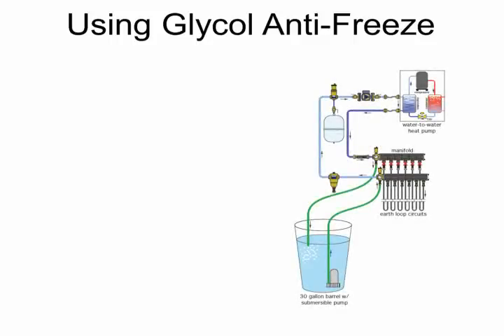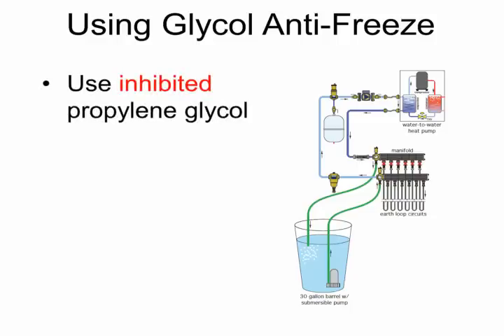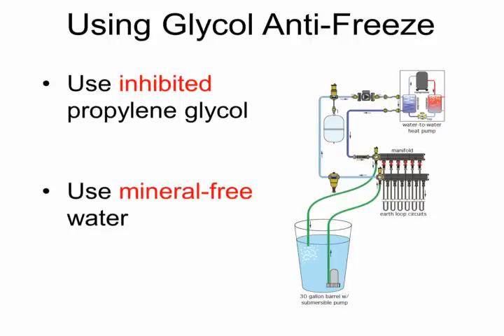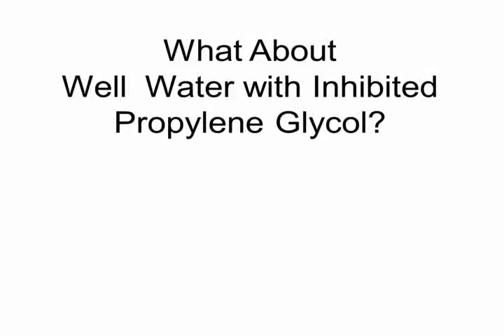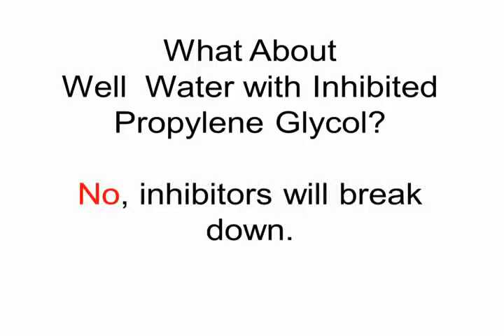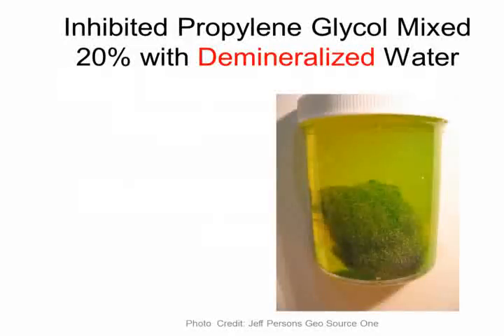Now, we mentioned glycol. How about using glycol with antifreeze? Very common with systems in the United States and Canada. Okay, so here's a geothermal system being filled with fluid. We recommend inhibited propylene glycol, not uninhibited, but inhibited propylene glycol, and mineral-free water, not untreated water. Because if you use untreated water, say well water, with even inhibited propylene glycol, the inhibitors can break down. So don't do that. And Jeff Persons, our friend who showed us in a couple of webinars ago, showed a quick experiment.